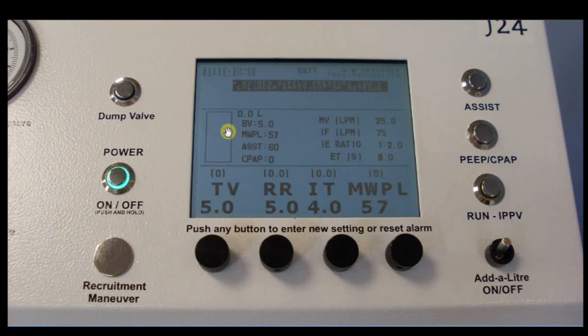What this means is that you can actually control very carefully your circuit volume, so that when an anaesthetic is started you have a big circuit volume, the patient's allowed to take big breaths, and then once they're asleep and finally controlled, you can reduce the circuit volume, which improves your time constants for changing vaporizer settings.